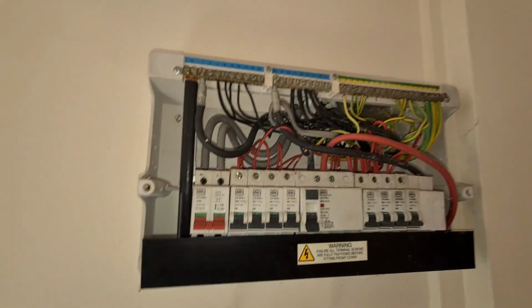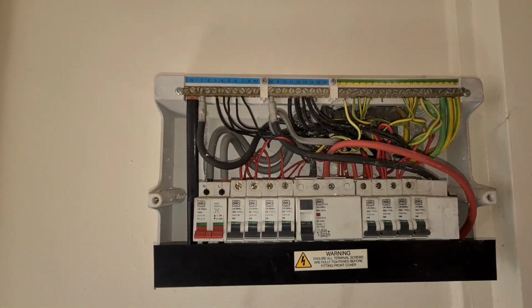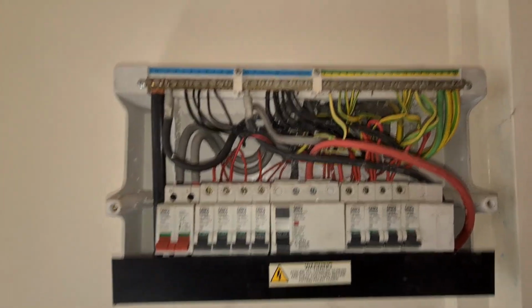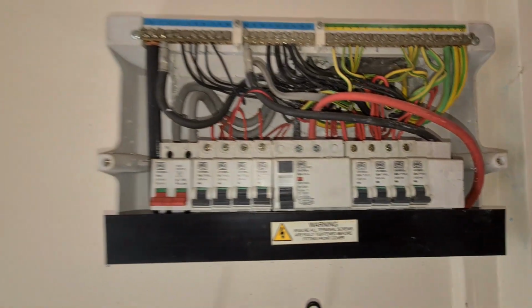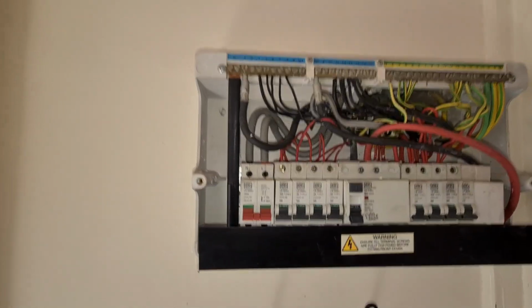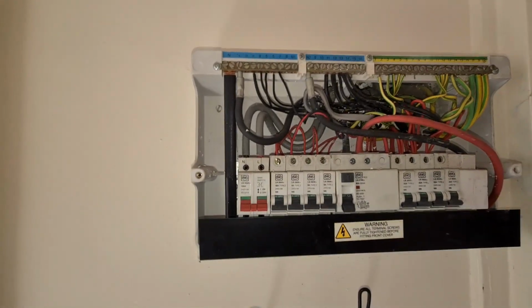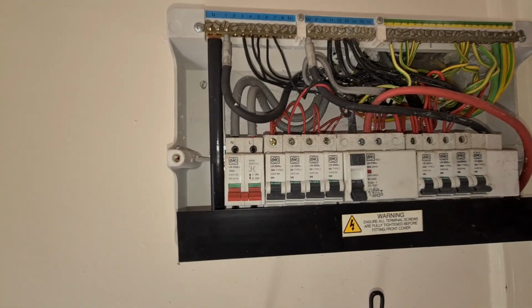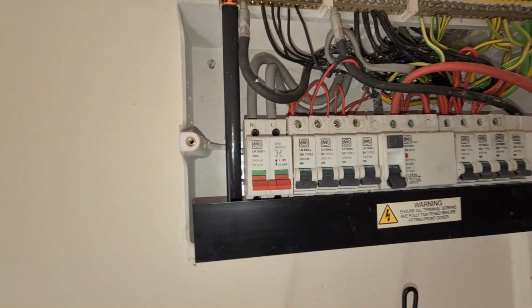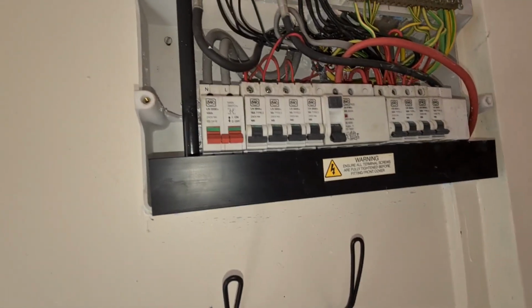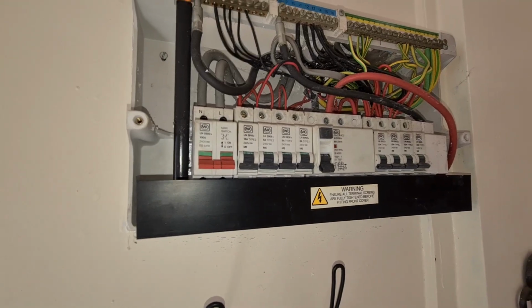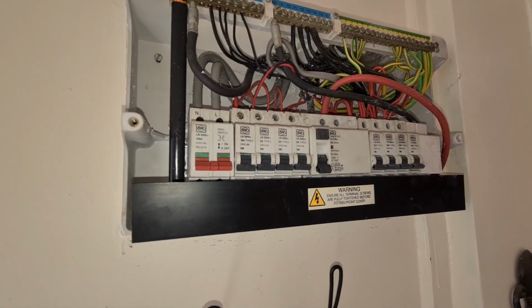This is the current consumer unit. It's a 16th edition board, so we do have an RCD on there for the socket circuits. The lighting circuits, not so much. The lights have actually stopped working on this one, and we'll explain why as we move through our inspection. We're just going to run through it all visually together, and then break some of the testing down, and I'll show you little bits of that as well.